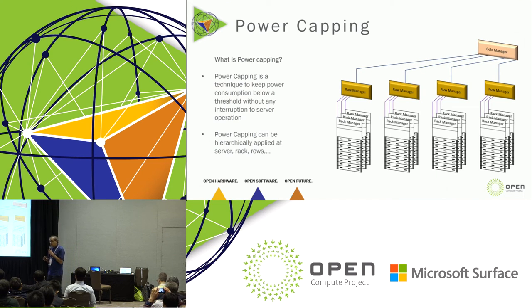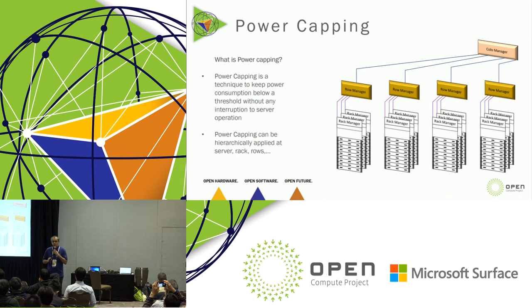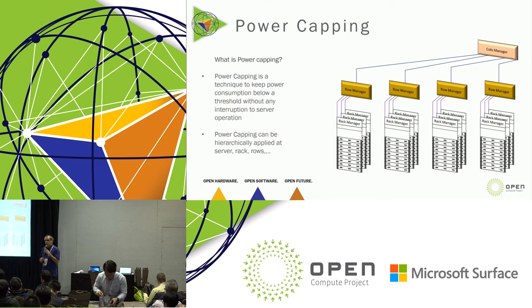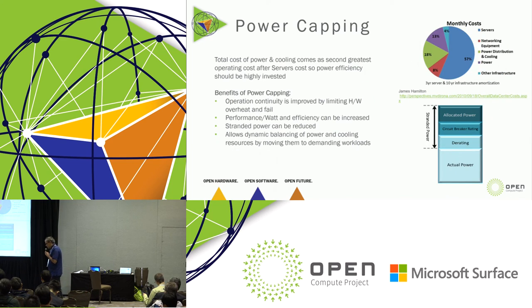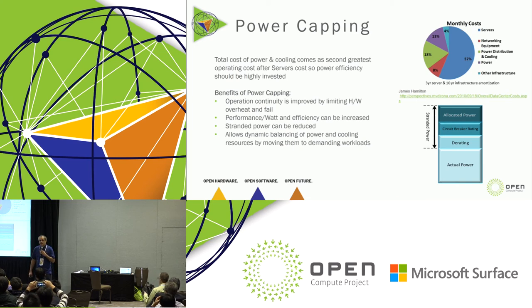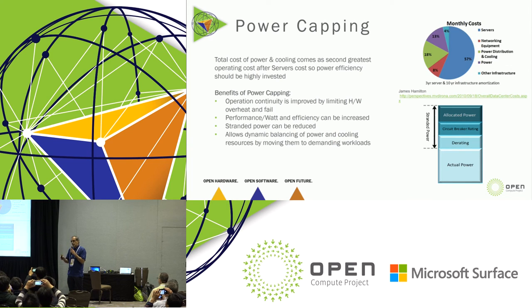With power capping, we are lowering the limit of power consumption. The idea is to keep the operation running — we don't want any interruption. But for a short period of time, a performance degradation is acceptable as long as there is no complete interruption to the service. As this graph shows, after server costs, the total cost of power — including electrical power and the power required for cooling — comes as the second greatest cost at the data center.